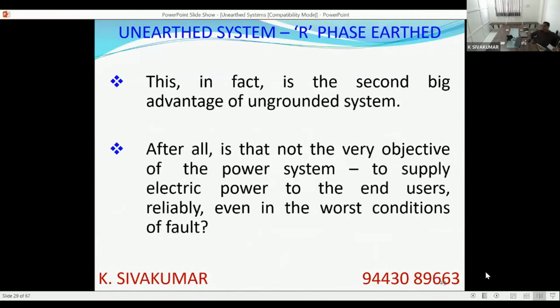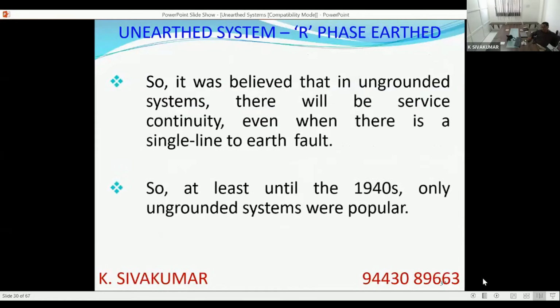So this was perceived to be the second advantage of the ungrounded system. I say this was perceived. Power system engineers will agree with me, the very objective of the power system is to supply electric power to the end user, even in the worst conditions. Even in the worst condition of a single phase to ground fault, there is no interruption. Power supply will continue to go to the customer in an ungrounded system. So not surprisingly, it was believed that in an ungrounded system there will be service continuity even when there is a single line to earth fault. So at least until the 1940s, perhaps until the Second World War, only ungrounded systems were popular.